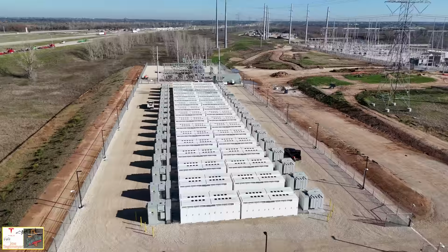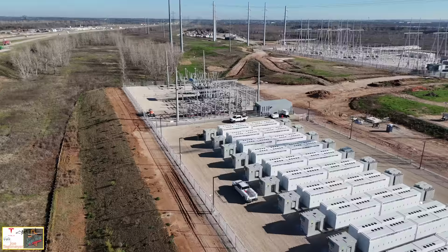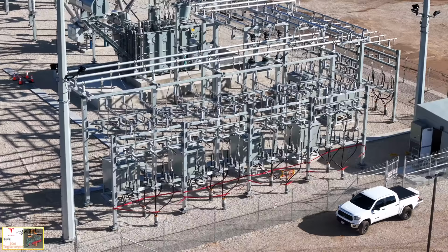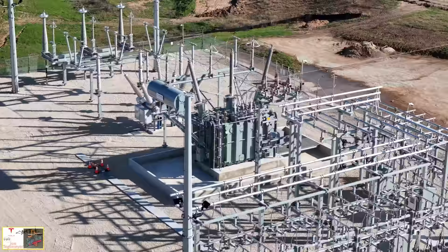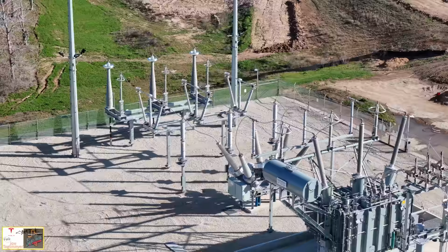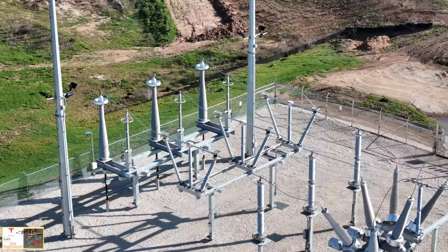Now, an interesting development here today concerning the Megapacks is that it looks like the Megapacks themselves connected to the building are not connected. We can get a close-in view here. You see those open kind of breaker arms. They're all kind of in the middle of the screen, those black items that are kind of hanging down. They would need to be up to be able to connect the Megapack to the main building. However, a big change is right here. The three swivel double-ended disconnects have now been turned and they are connected.